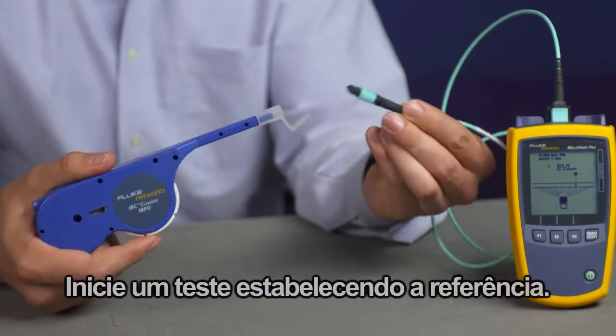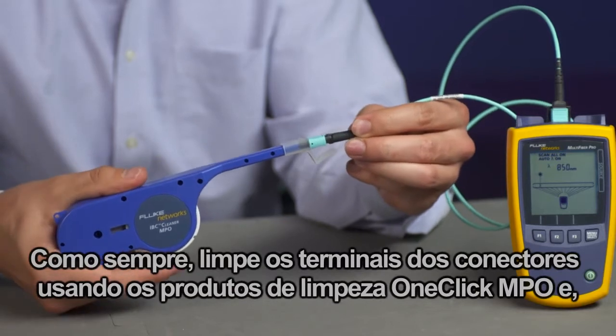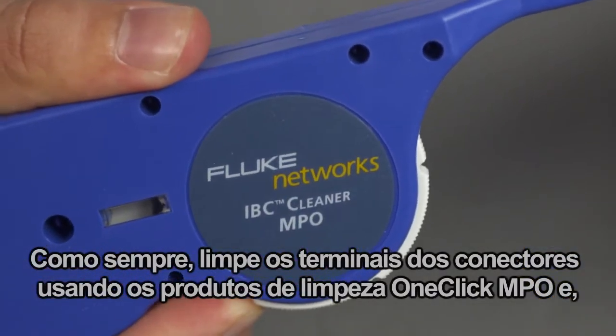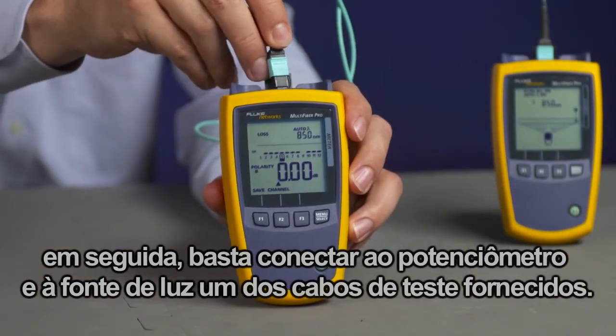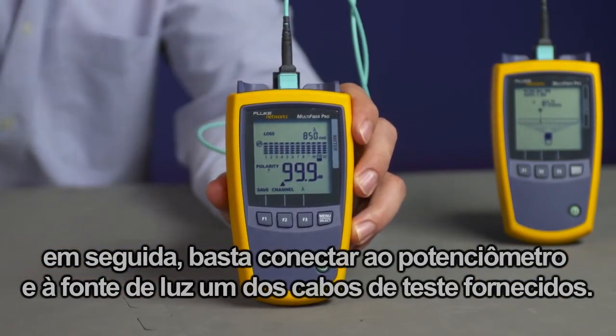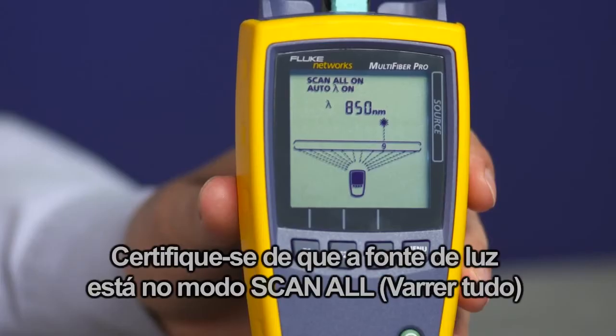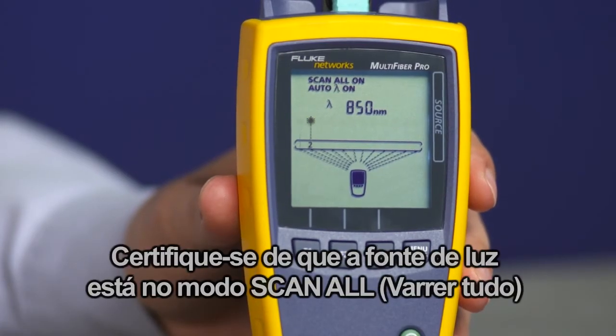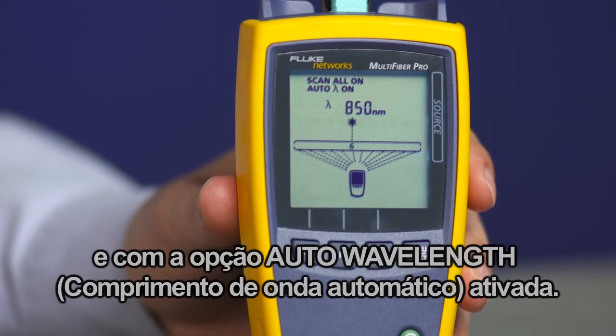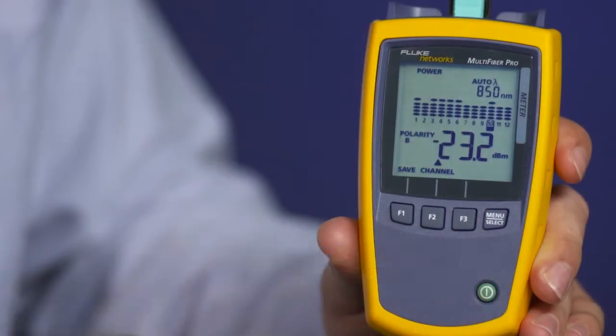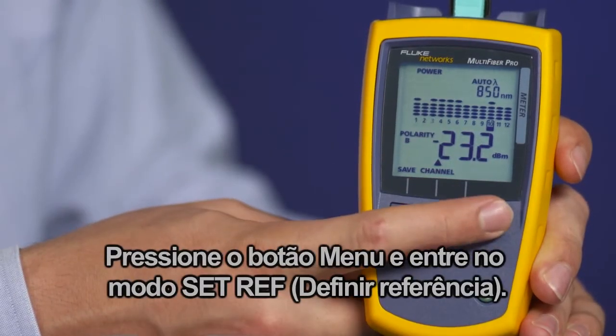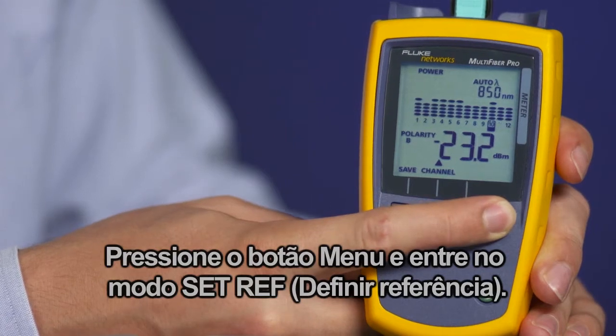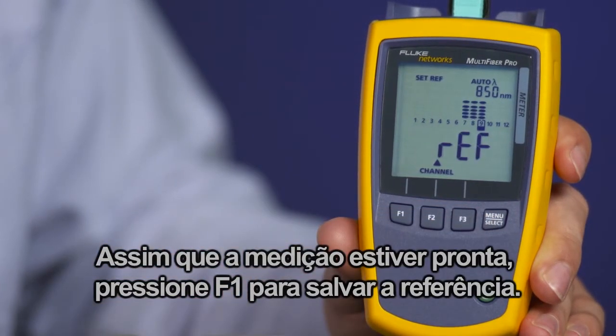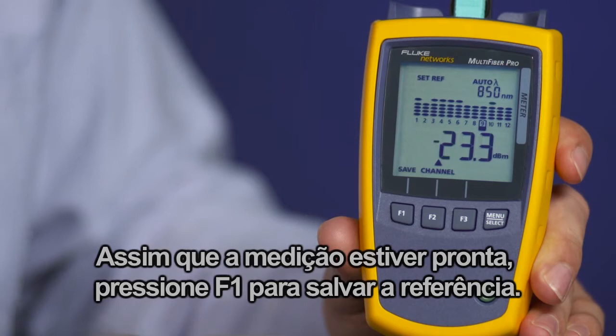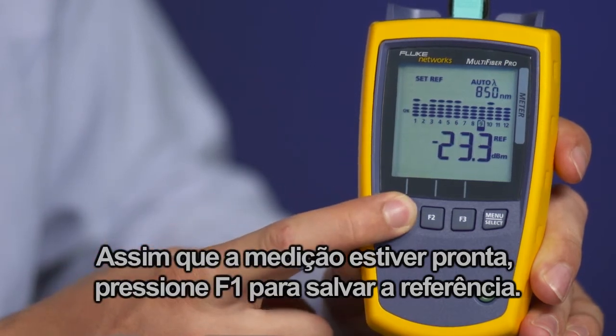Begin a test by setting the reference. As usual, clean the end face connectors with our one-click MPO cleaners. Then simply connect one of the given test cords to the power meter and the light source. Make sure the light source is on scan all mode with auto wavelength on. Press the menu button and enter set ref mode. Once the measurement is ready, press F1 to save the reference.